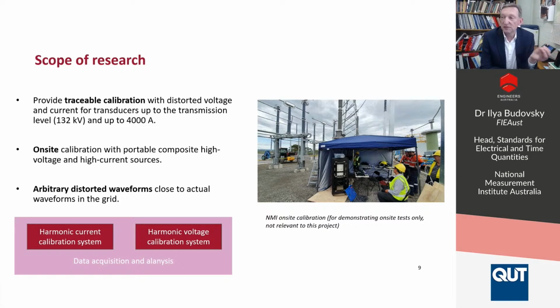Very importantly, and this is totally new, we will be providing this calibration on-site and with composite signals that contain a fundamental up to 132 kV and 4,000 amps, and any number of harmonics up to 10 kilohertz. The picture here shows an on-site calibration, but that's not for this project. This is just for illustration. What we want to do is come to where it matters, with sources that create those arbitrary distorted waveforms and a measurement system that can calibrate, traceably, any instruments used to measure them.